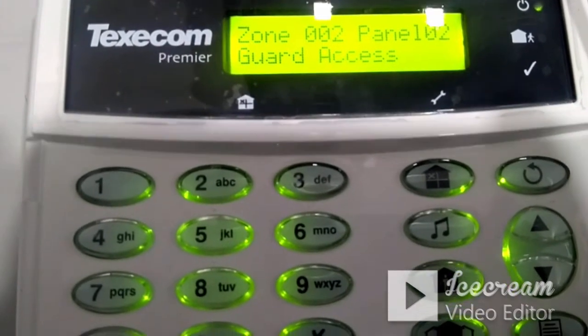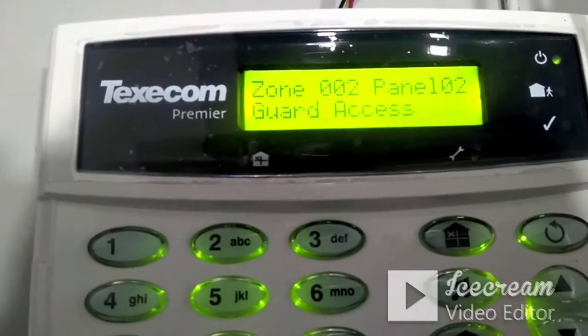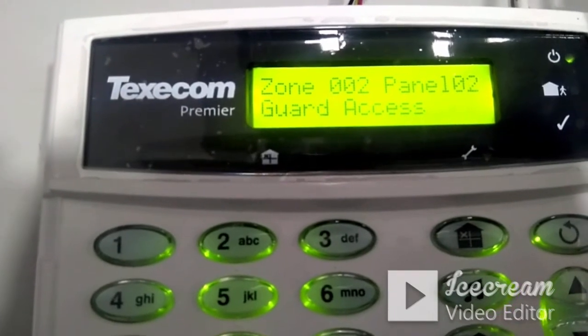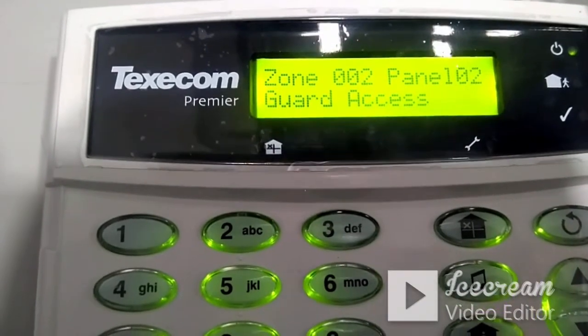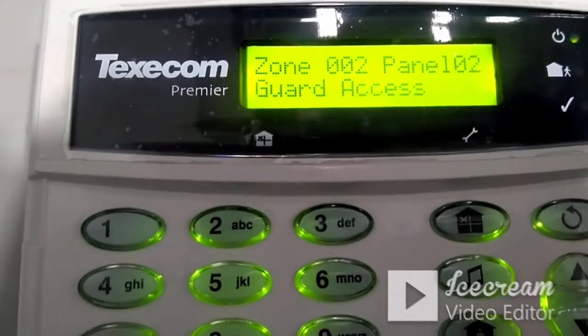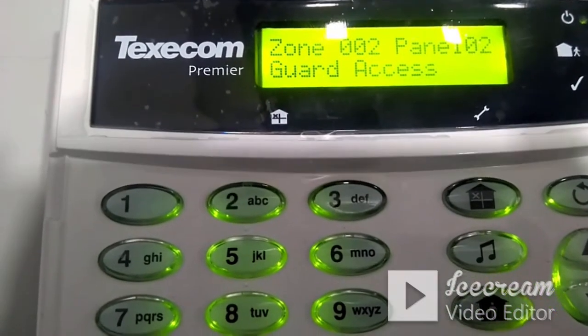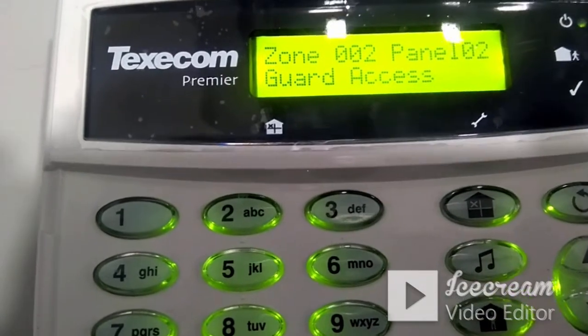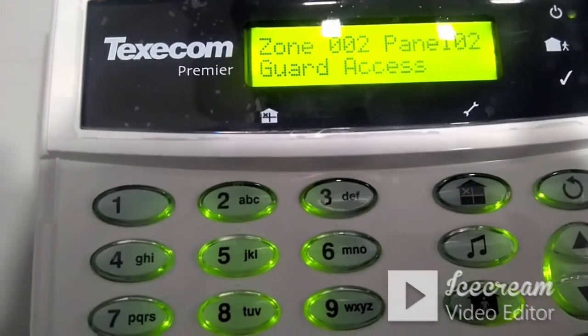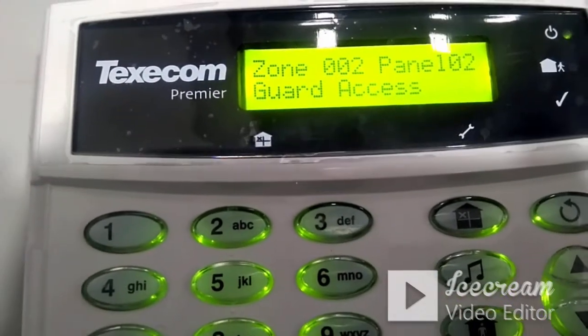The next day when you return and open the shutter, the shutter contact zone activates. Since entry delay is programmed, the panel waits until entry delay ends. You then cross the PIR area — zone 2 also activates — but the panel will not go into alarm until entry delay completes. Within this time, you can enter the office or shop and disarm using your password. So the exit delay assigned to the exit zone is applicable to the Guard Access zone both when exiting and when entering the premises.